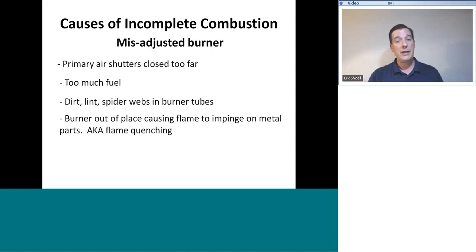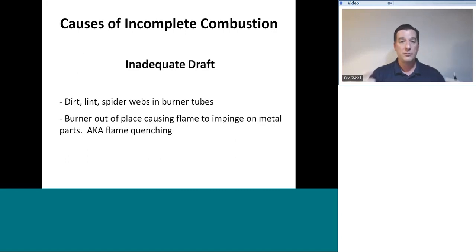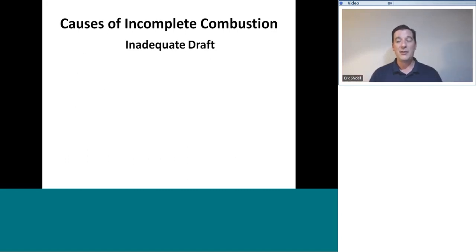The burner out of place. Remember our fuel triangle? Remember the heat side of the fuel triangle, the combustion triangle? If your burner is supposed to be pointed like this, and the flames are supposed to be pointed upwards, and the whole burner tips to the side, and its flames are pointed to the side, and those flames are burning on a metal surface, that metal surface will reduce the flame temperature. It's a process called flame quenching. When flames impinge on a metal surface, we get incomplete combustion, very high carbon monoxide levels as a result. And of course, that's our jurisdiction, right? We control the alignment of the burners.